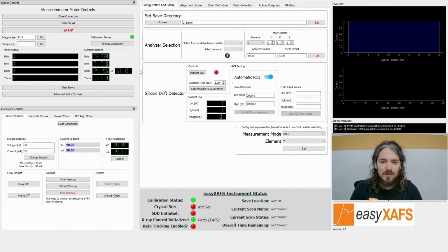The motor controls for controlling the position of the components are at the top left. At first power on, the motors take a couple minutes to calibrate. Here the calibration has been completed already. Control of the X-ray tube is at the bottom left. Here we can change the X-ray power setting and open and close the shutter. Again, when you first power up, you have to warm up the X-ray tube, but for the demo, we already have the X-rays warmed up to 40 kilovolts and 20 milliamps.